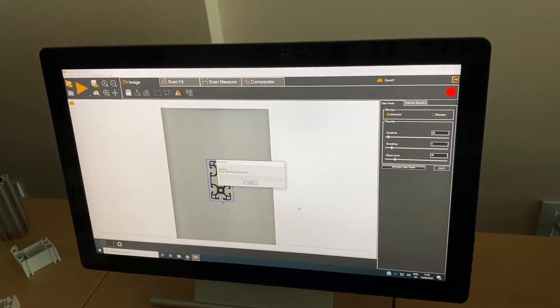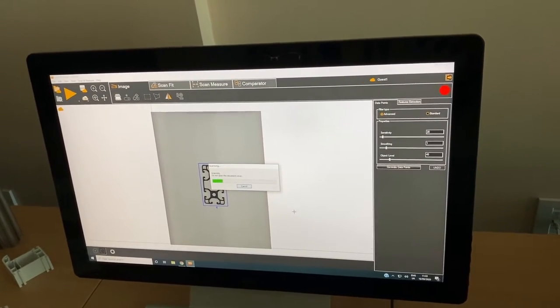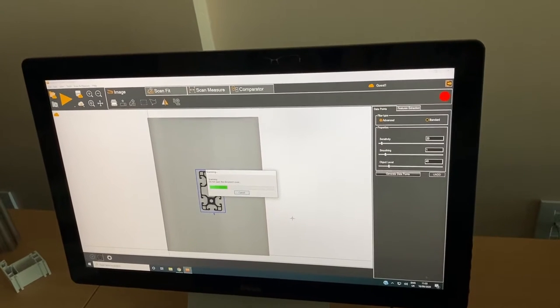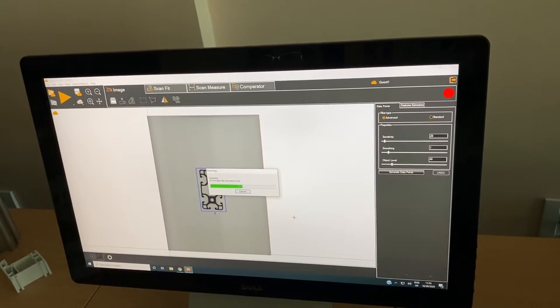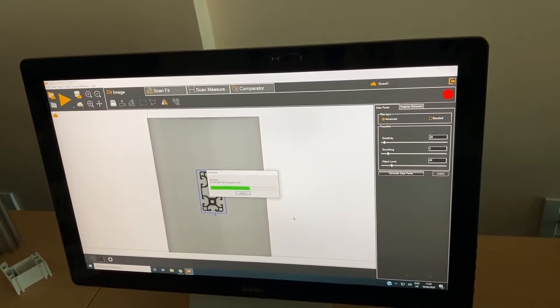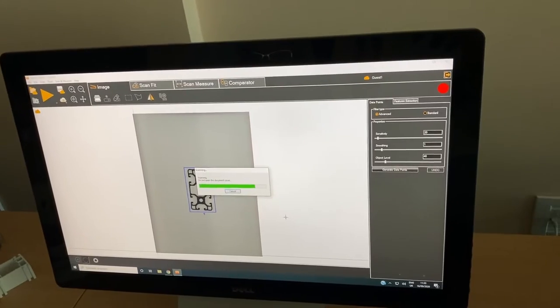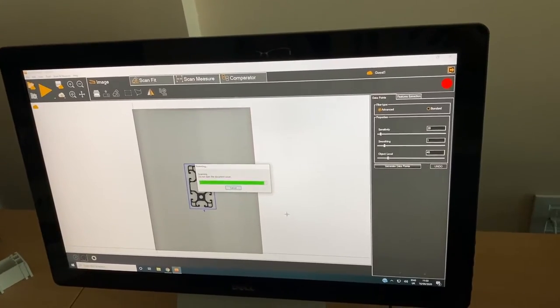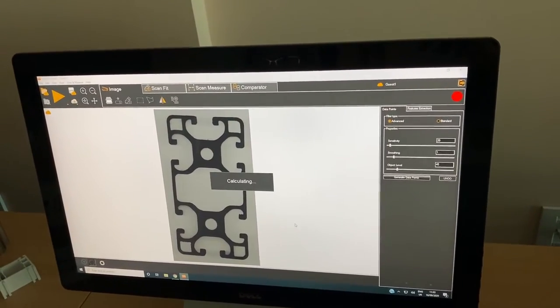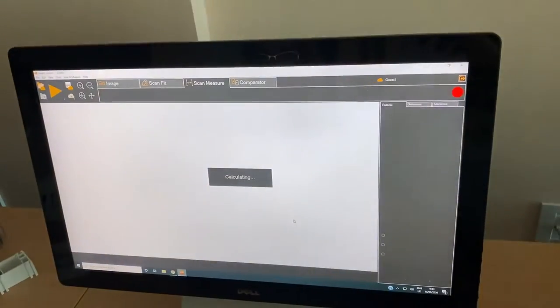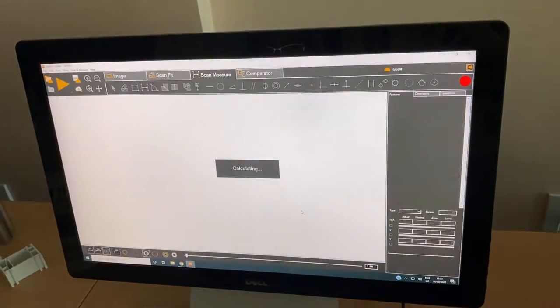On the scanner we can also put several pieces of the profile, all from different profiles, and they will be measured with one scan and reports will be generated for each profile.